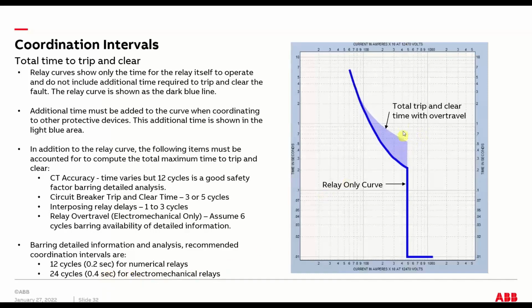of time interval between devices was about 0.4 seconds. For a numerical relay, you can cut that at least in half to 0.2, and most of the times you can go much lower than that to probably no less than 0.1 second or 6 cycles. That's probably cutting it to the bone.